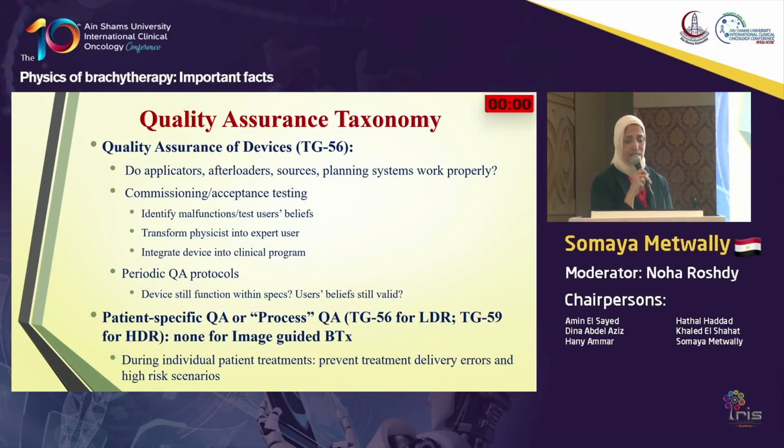use your machine. Transform the physicist into an expert user. You have to give your physicist training on how to use this machine, and also how to calibrate your machine before you start to treat patients. Integrate the device into the clinical program. You have to enter your machine into a specific program for quality assurance. You have to do this procedure before you start to treat your patient.